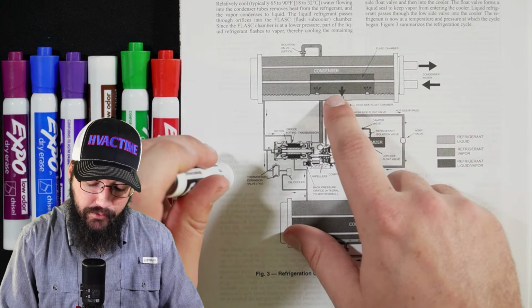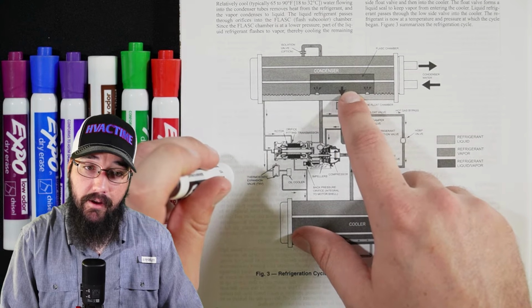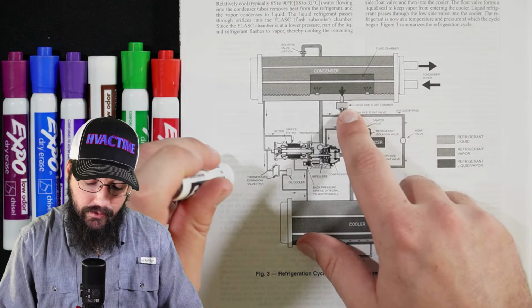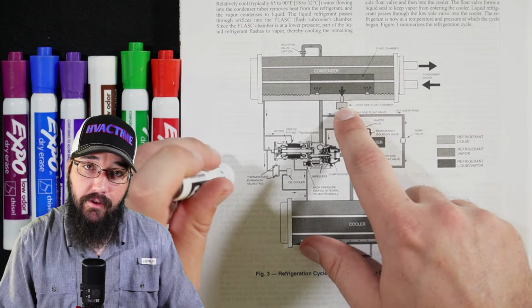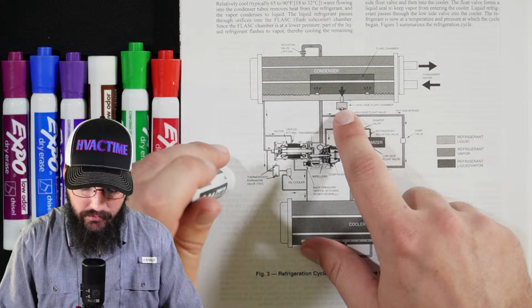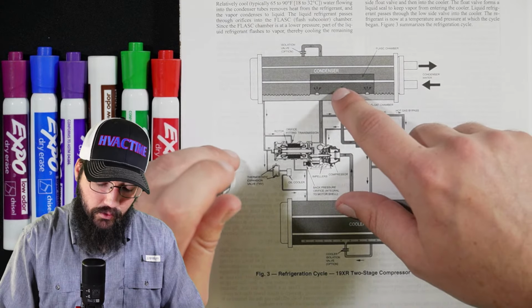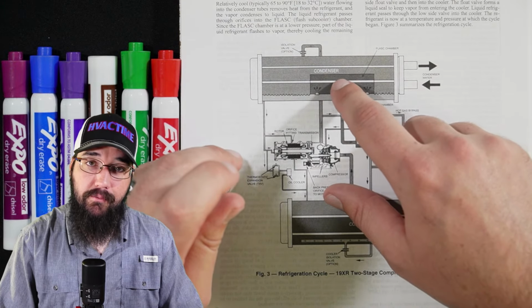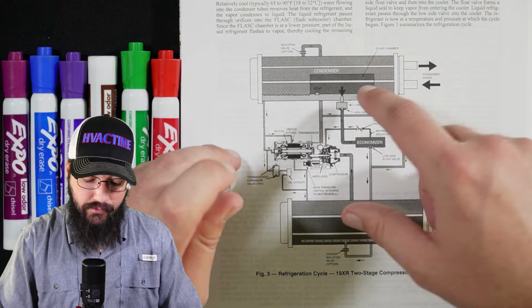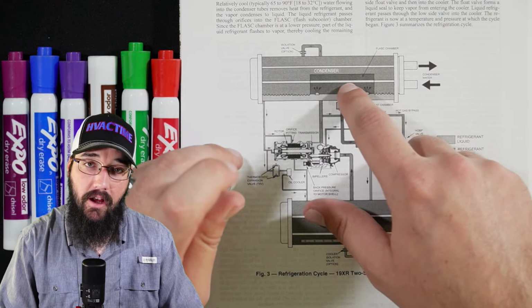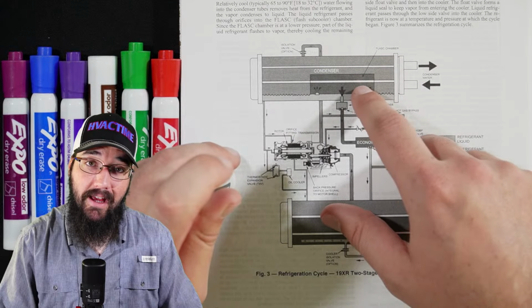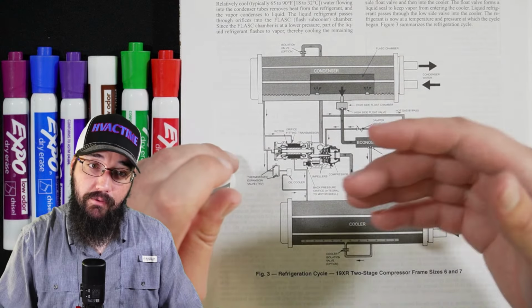So we flash off, we enter into this flash chamber called a FLASC chamber by Carrier. So the liquid refrigerant entering this chamber stays at the bottom, and it drains into the metering valve drip leg, or the float valve chamber would be another way to say that. And then the vapors that flash out of that liquid refrigerant start to collect up here in the top of the chamber. Now this chamber does have condenser tubes running through it.